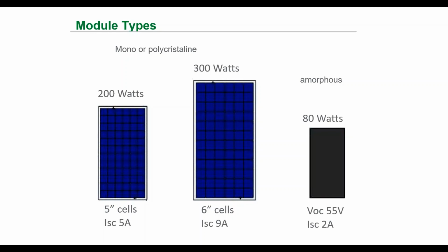One question has come, similar to one asked previously. We are doing a simulation on a DC microgrid using PV cells, and we are getting negative power on the grid. What's the reason? The grid is supplying power to the load because your PV system is generating less power than the load requires. For example, if your PV is giving 1 kilowatt and load is 2 kilowatt, then definitely that 1 kilowatt will be drawn from the grid. You need to check your PV generation versus your load, and match or reduce the load relative to the PV, say making the load 900 watts if PV is 1 kilowatt. Then you will not see this negative value.